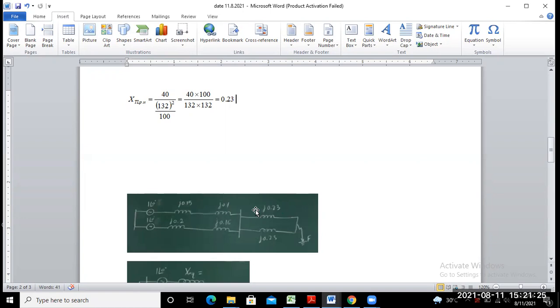Equivalent reactance, how can we find out for this system? How can we simplify the circuit? We want to represent a single source connected with whatever impedance is involved here, represented by a single impedance, with the fault taken at this point. We simply want to find out the fault current, that means voltage by impedance, is it not? So we want to convert all these reactance values into an equivalent form, simply connected through the source EMF value. So how can we convert this value of reactance into equivalent form? Can you simplify the circuit?